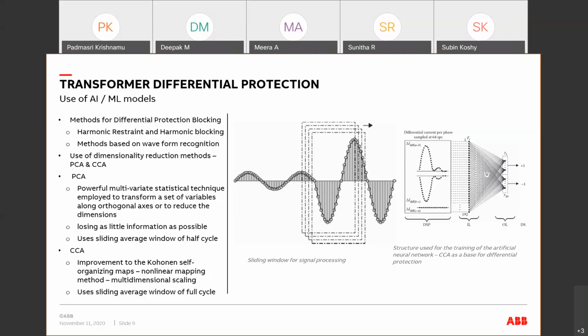The other one we are very familiar with, and which is the most used differential principle, is the percentage differential principle. It improves the performance of the differential protection because it compares the operation current and the restraining current, obtained by vector addition and subtraction. This reduces the negative effect of saturation in the current transformers. But there are some methods to further avoid incorrect operation due to inrush currents during transients affecting the magnetic flux of the power transformer. The first solution was to include an intentional time delay in the differential relay to halt the relay operation for a certain time interval, typically of the order of 16 milliseconds. But this is a major disadvantage, because in order to eliminate the inrush condition, you are delaying the tripping of a true fault condition.